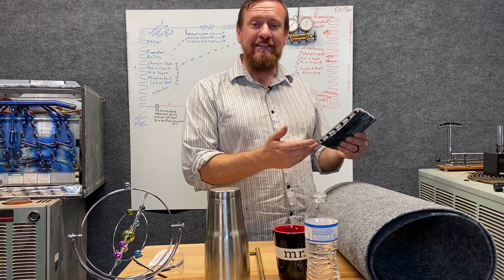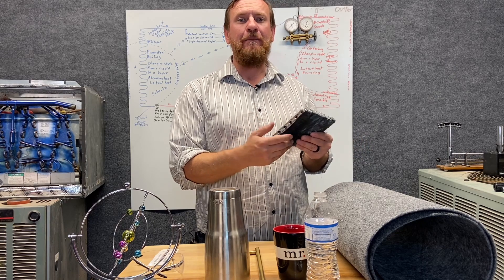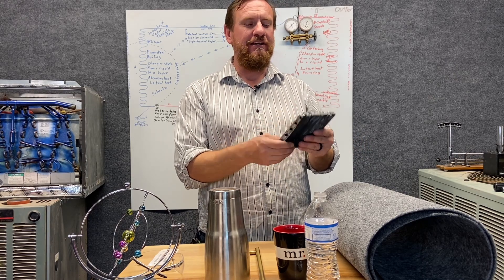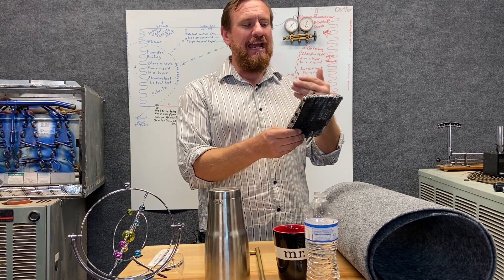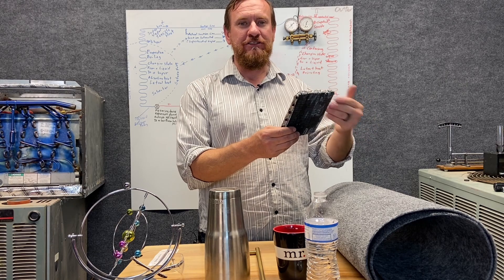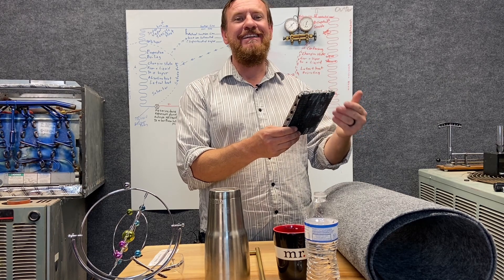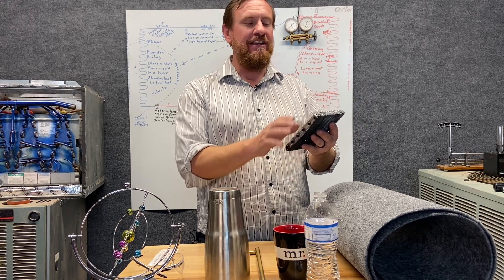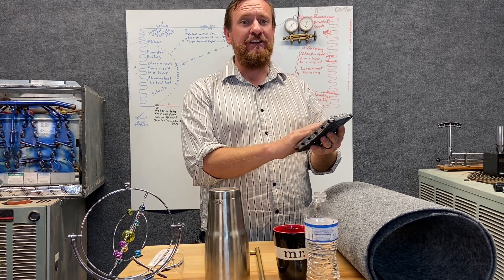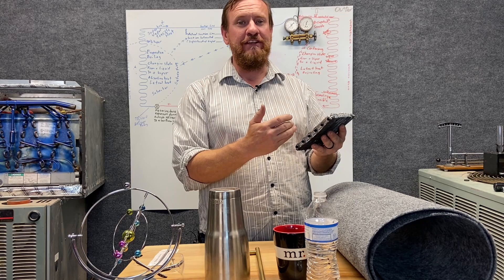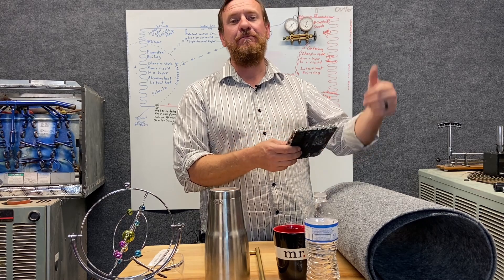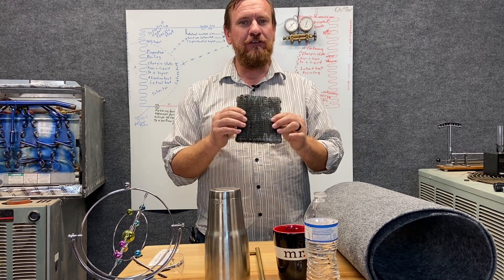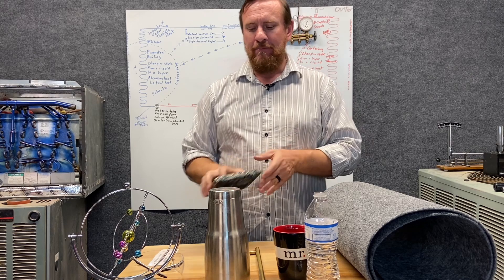Outside, it's the same thing but the opposite effect. The refrigerant is a warmer temperature than the air, so we're moving air across the refrigerant to take the heat out of the refrigerant and release it to the air. If the coil gets dirty, we don't transfer heat very well and our pressure goes up. So that heat transfer is important — this is why we use that metal.